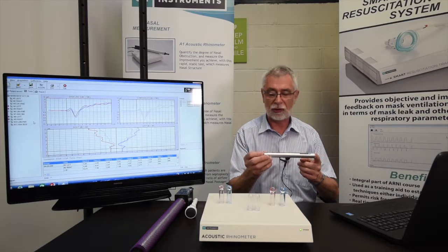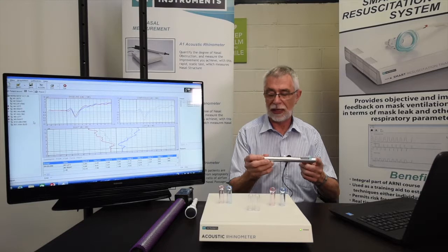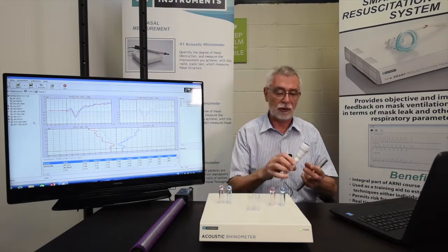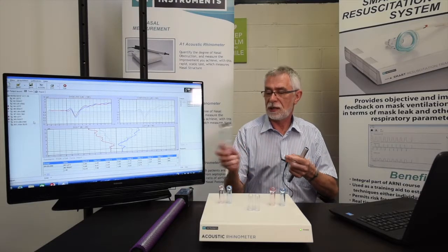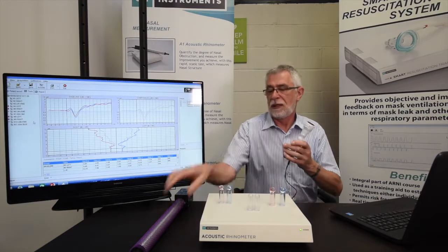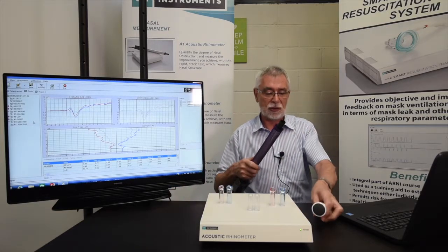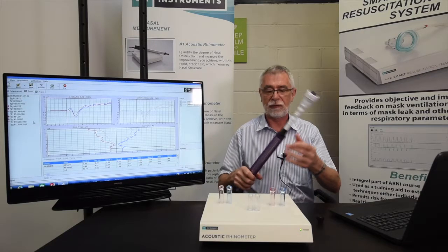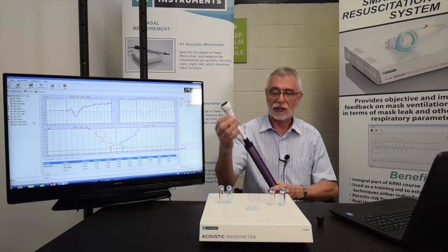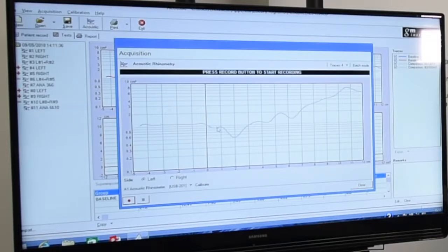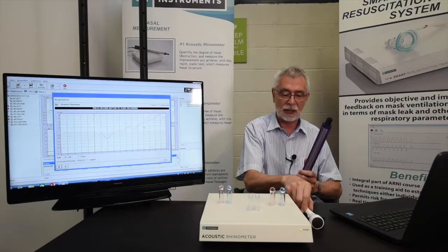should get a straight line going across the screen running parallel to the horizontal axis. And if you use the artificial nose, which is what this is, which goes into the end of the sound tube, you can make a measurement using the artificial nose and compare the tracing that's produced against a sample trace that is provided on the screen as a background trace.